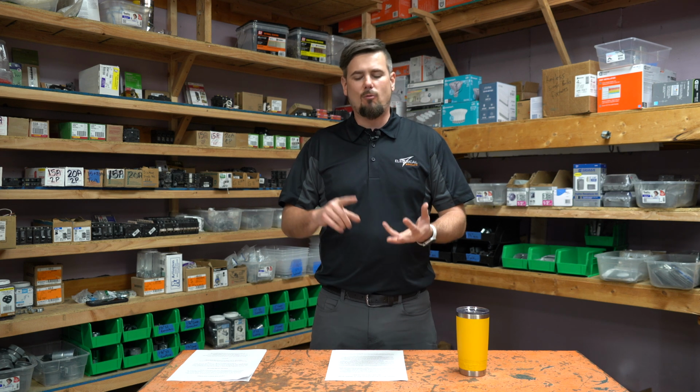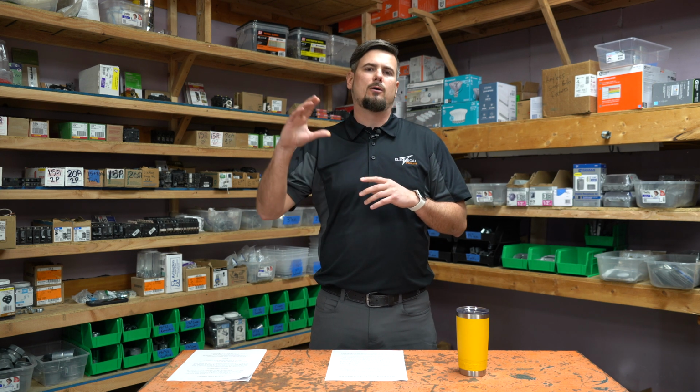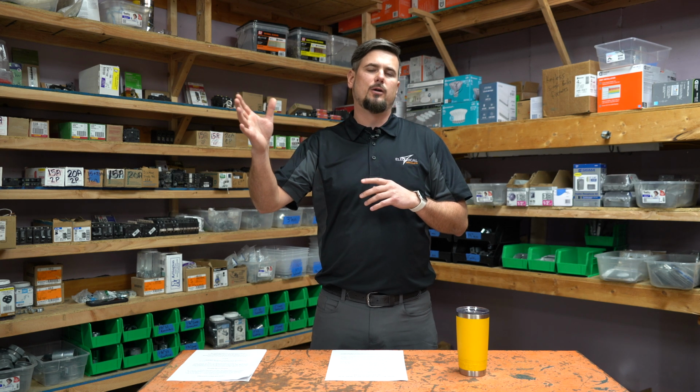The last thing we're going to talk about is smoke detectors and carbon monoxide detection. Those are very important. Code's really enforcing those. Every single bedroom needs one. Every hallway outside of a bedroom, every living room, every basement, and every attic with equipment like a water heater or furnace needs them. So make sure that you have those in those areas and at least one carbon monoxide detector, which you can usually do in a combo outside in the hallway of the bedroom or in the living room.